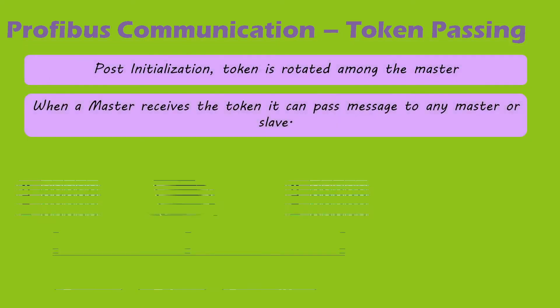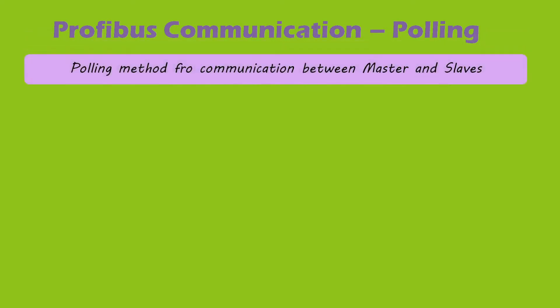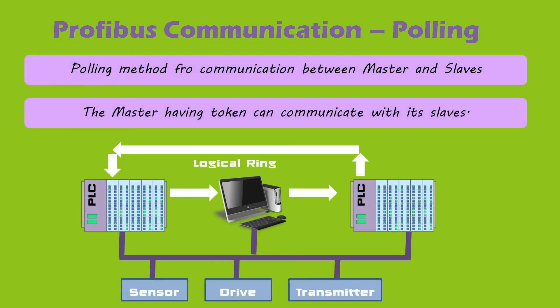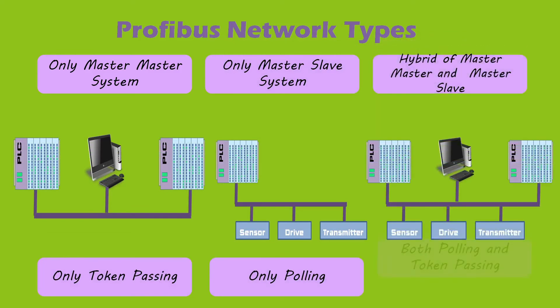Post-initialization, the token is rotated among the masters. When a master station receives the token from the previous master, it gets the right to pass messages to slaves as well as other masters. The polling method is used for communication between a master and its slaves — specifically by the master that currently holds the token. A Profibus network could be a pure token passing system (master-master), a pure polling system (master-slave), or a hybrid of both token passing and polling in the same network.